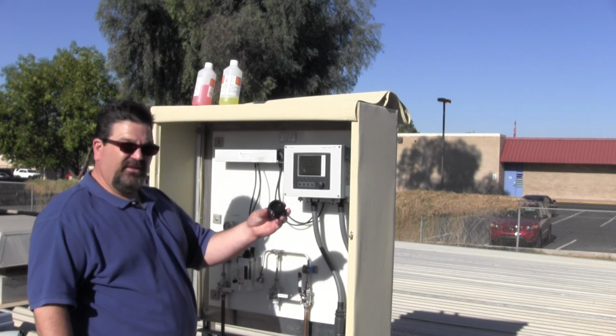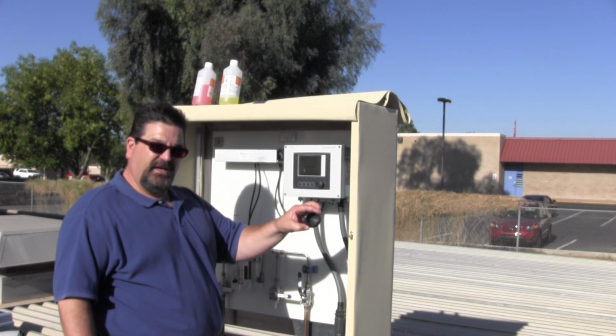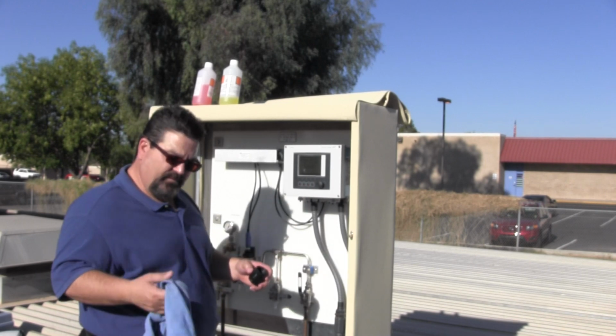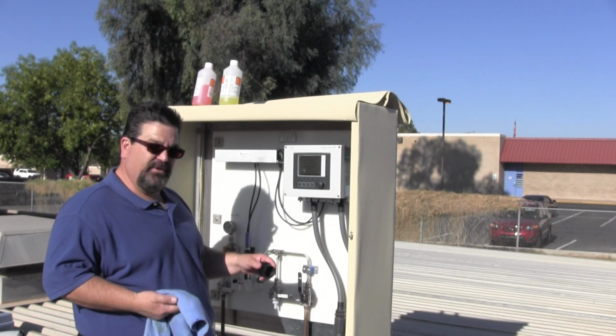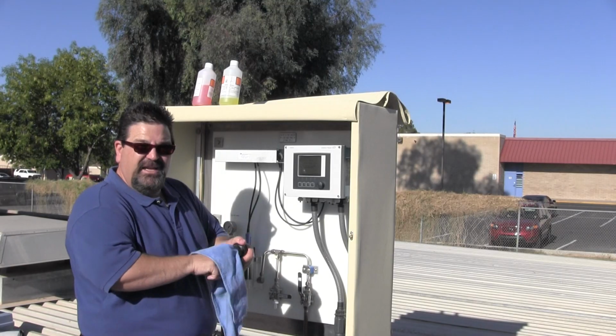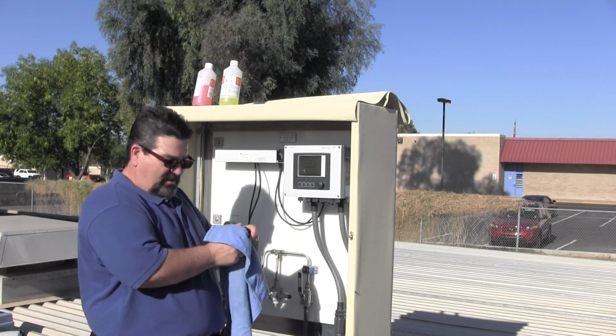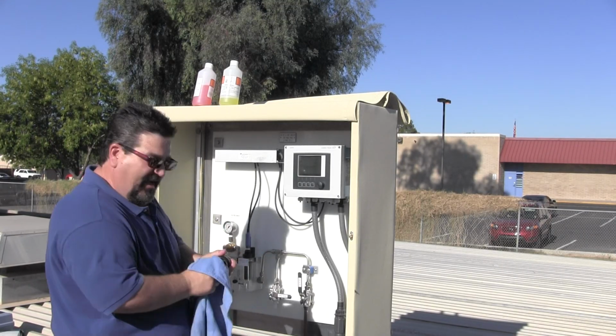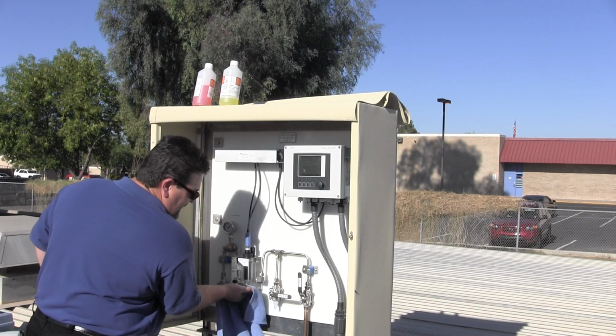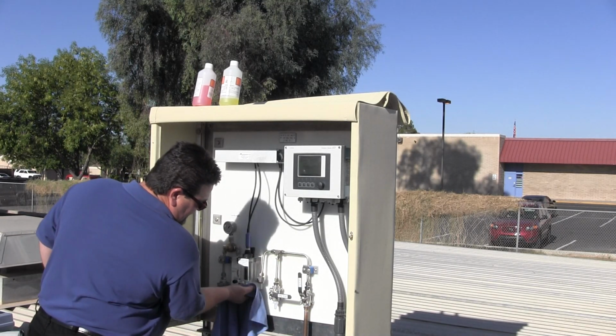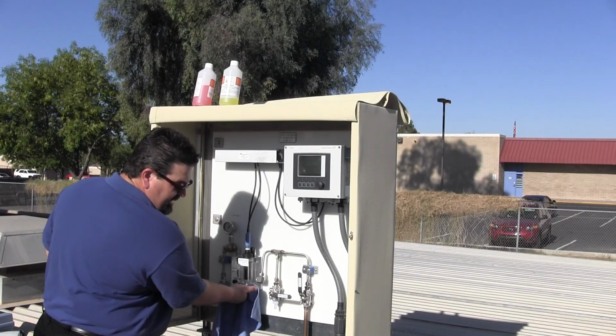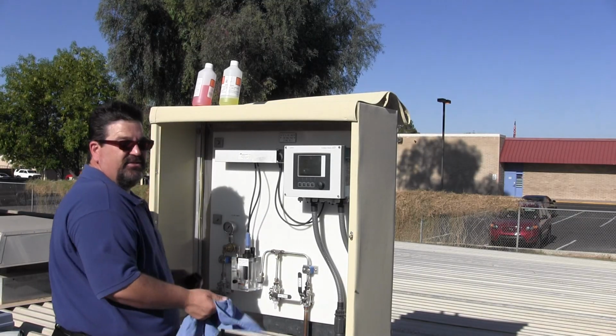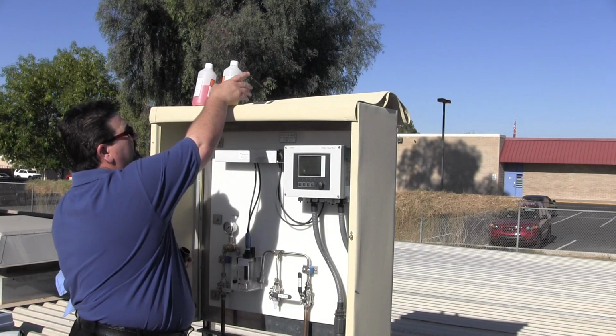You can see there's a shallow side of the cup and a deep side. The deep side's used for our pH buffers in the calibration process. You want to clean this cup out as well as you can and dry it out. You also want to dry out the cavity and the tip of the pH electrode. Get the most of the water out of there so you don't poison the pH buffer or dilute it.